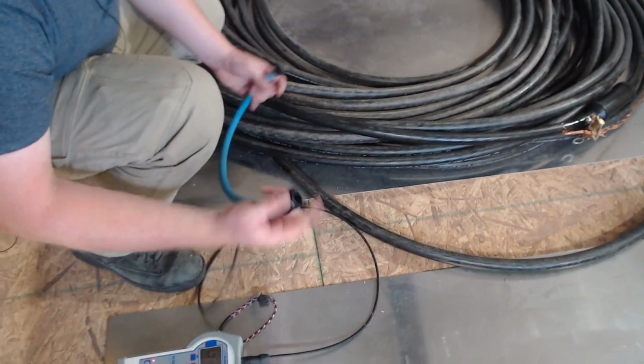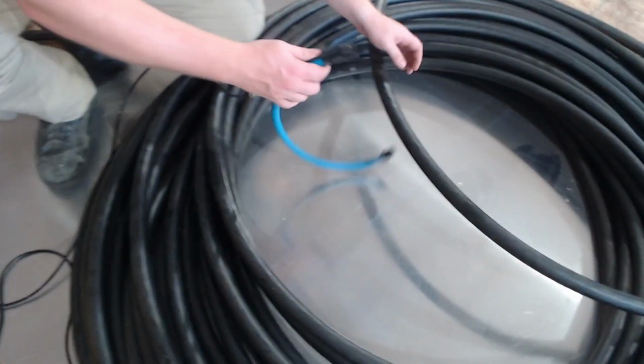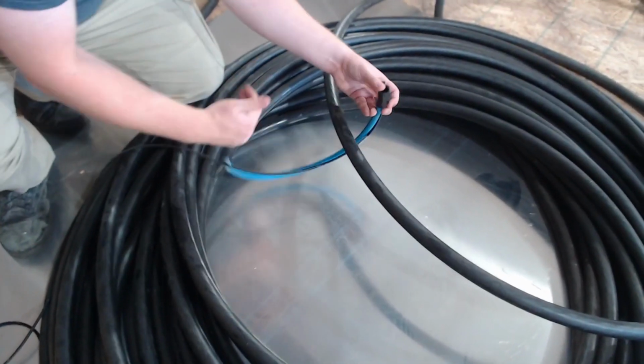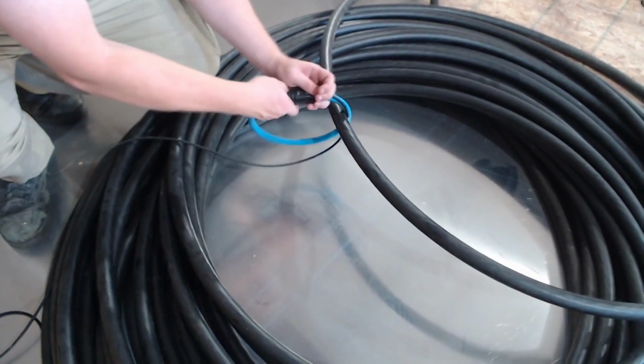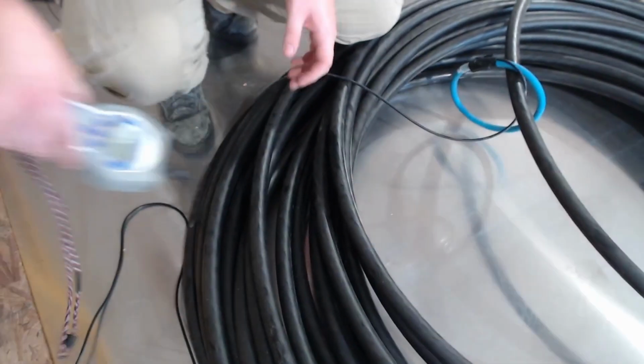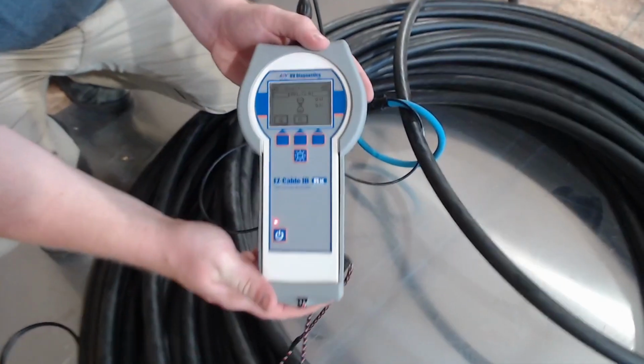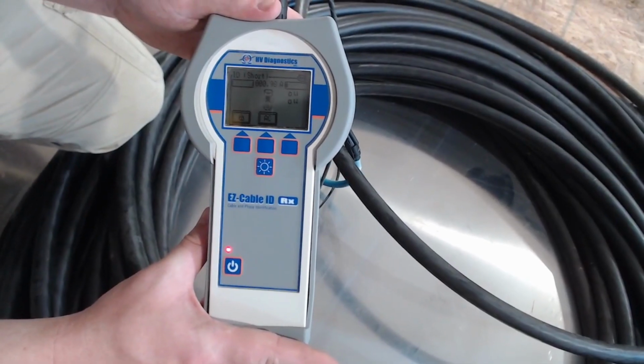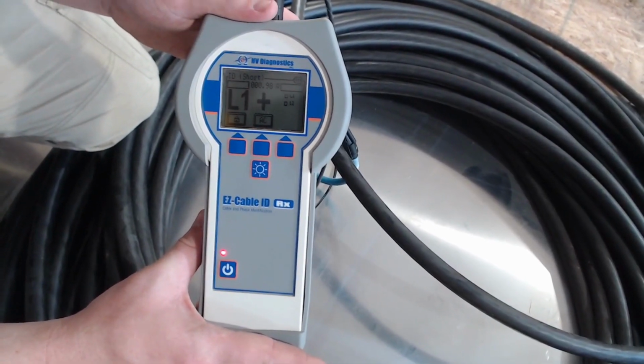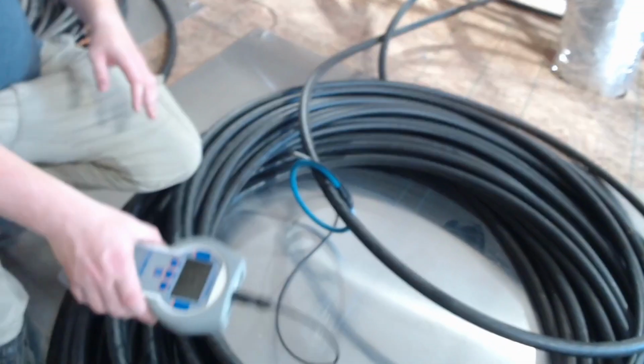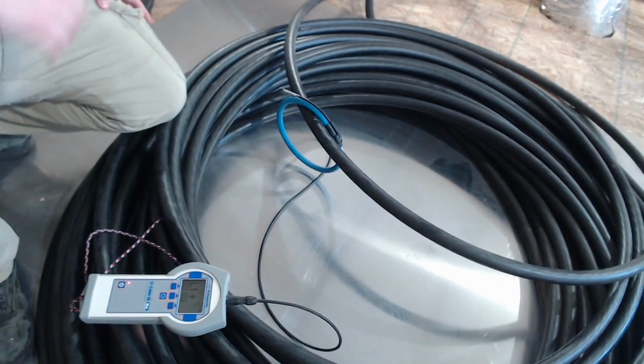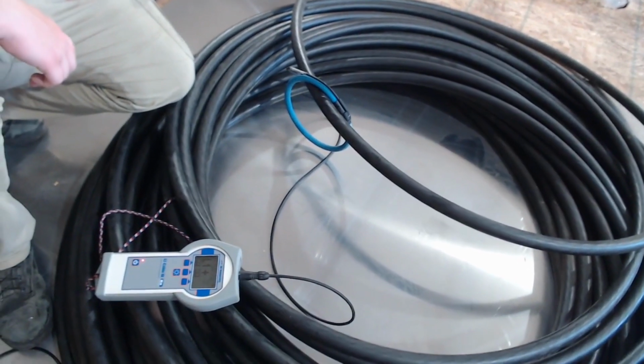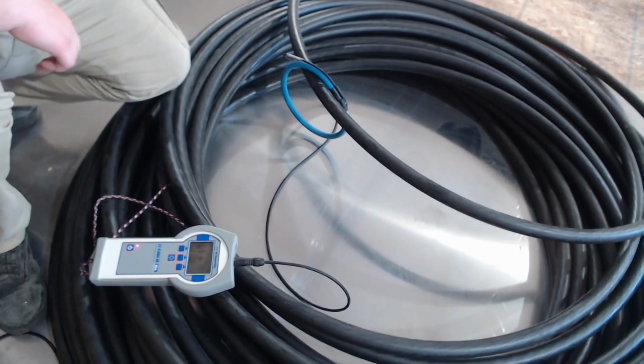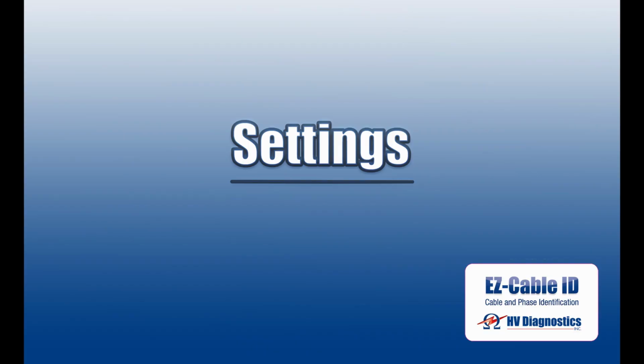So now if we go over to our other cable over here, it should just go straight into reading L1. There we go. L1 positive. That's the one limitation to inducing into the shield, is that you lose a lot of amplitude when you induce current through the air with the CT clamp versus inducing current through the conductor with the direct mode.